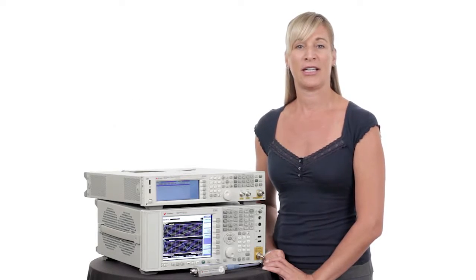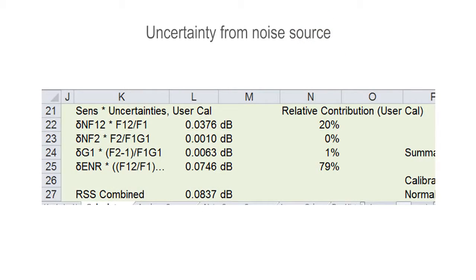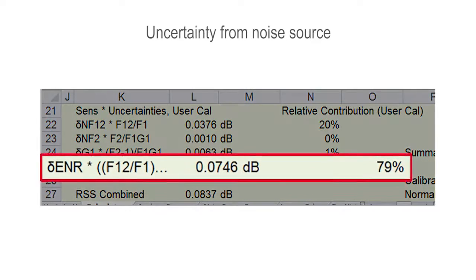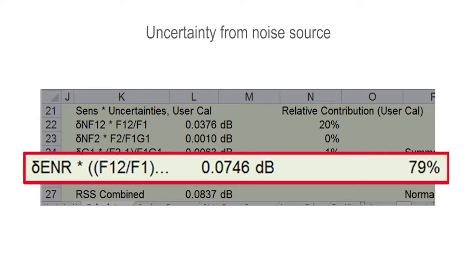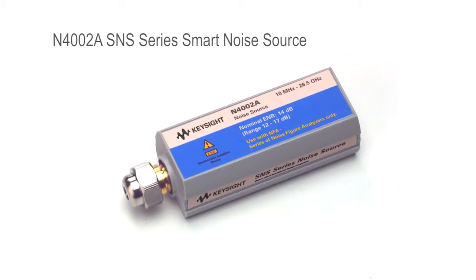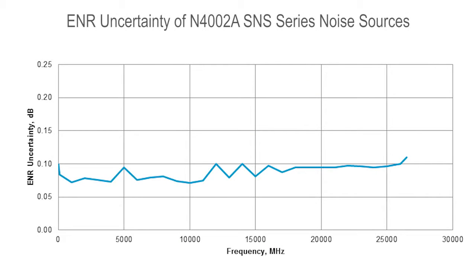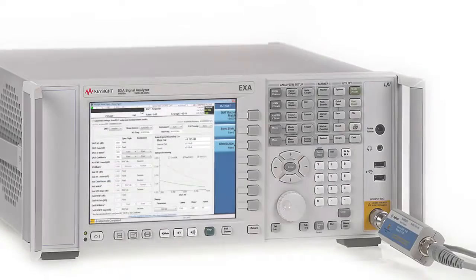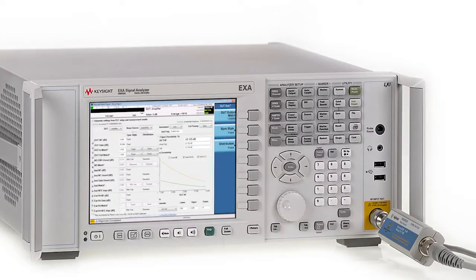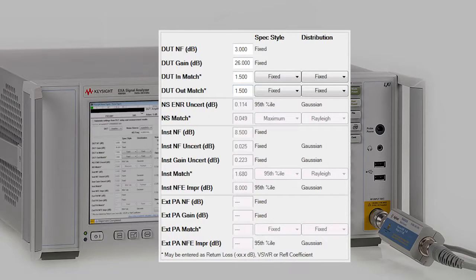Let's first take a look at the Keysight EXA's noise figure application. Overall uncertainty is a key performance feature when making noise figure measurements, and the noise source is the largest contributor to that uncertainty. Keysight SNS series smart noise sources have the industry's lowest overall uncertainty, plus they're easy to use. You simply connect to the EXA and the instrument recognizes the noise source model and serial number, and downloads all of the ENR data automatically.